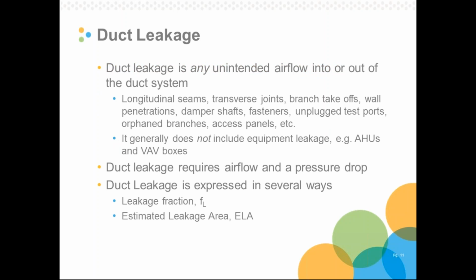So duct leakage is any unintended flow into or out of an air distribution system, or the ductwork. The vast majority of air distribution systems in C&I buildings are sheet metal ducts that are constructed on site. These ducts are not airtight. Duct leakage occurs throughout the duct system. This includes longitudinal seams, transverse joints, branch takeoffs, wall penetrations, damper shafts, fasteners, etc., etc. I can go on forever to talk about all the possible leakage paths. It generally does not include accessory leakage or equipment leakage, for example, air handlers and VAV boxes. Although, as an aside, it is often difficult to distinguish leakage from those components from duct leakage during regular testing.